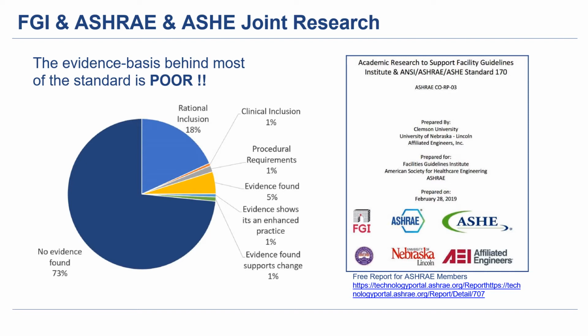This study came out last year on ASHRAE letterhead, and it actually says that 75% of healthcare ventilation requirements, and about 95% of the air change requirements, have no evidence basis, no clinical basis, and no rational basis. So there's not a very strong case for voluntary adoption of the air change standard, which is a very energy-intense standard. This really is one of the keys moving forward in healthcare.